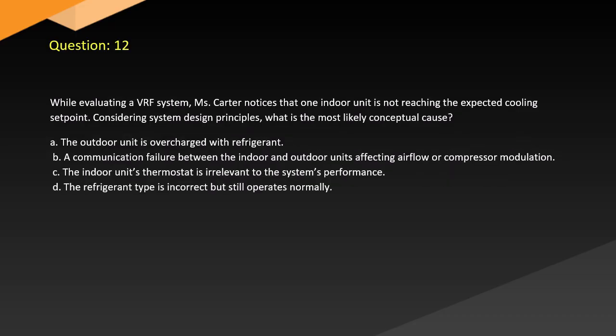Question 12. While evaluating a VRF system, Carter notices that one indoor unit is not reaching the expected cooling set point. Considering system design principles, what is the most likely conceptual cause? A. The outdoor unit is overcharged with refrigerant. B. A communication failure between the indoor and outdoor units affecting airflow or compressor modulation. C. The indoor unit's thermostat is irrelevant to the system's performance. D. The refrigerant type is incorrect but still operates normally.